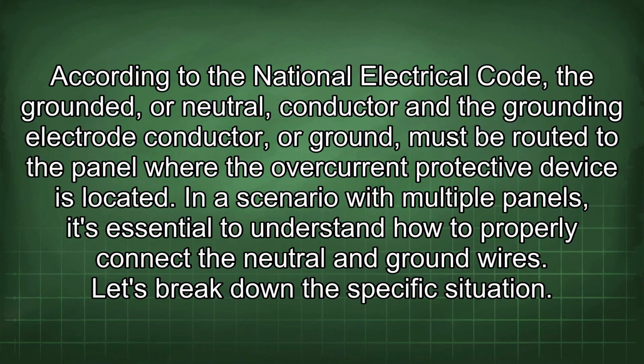According to the National Electrical Code, the grounded or neutral conductor and the grounding electrode conductor or ground must be routed to the panel where the overcurrent protective device is located. In a scenario with multiple panels, it's essential to understand how to properly connect the neutral and ground wires. Let's break down the specific situation.